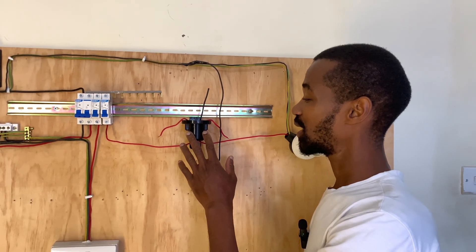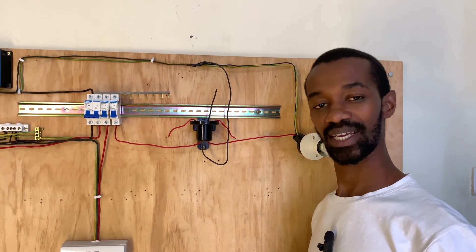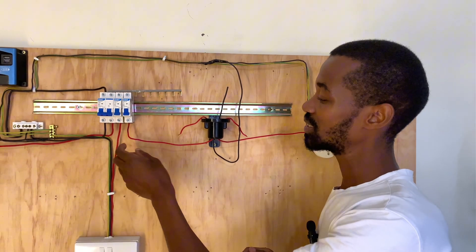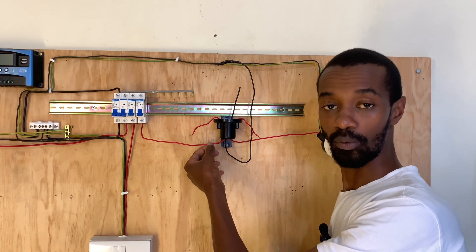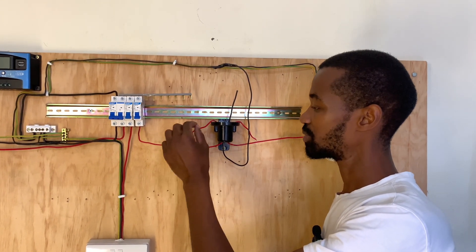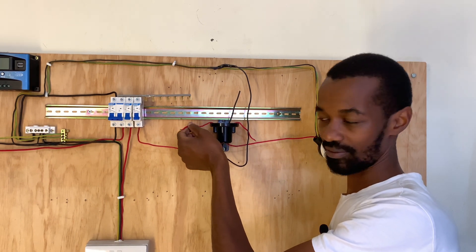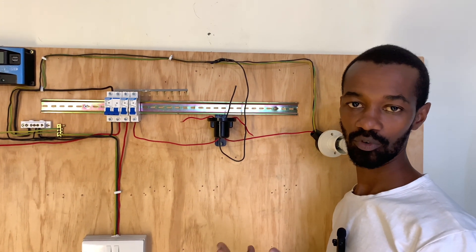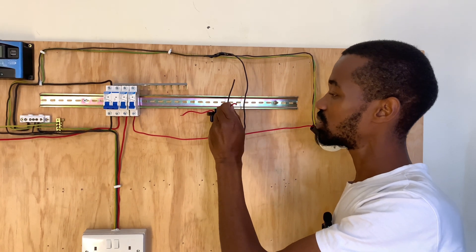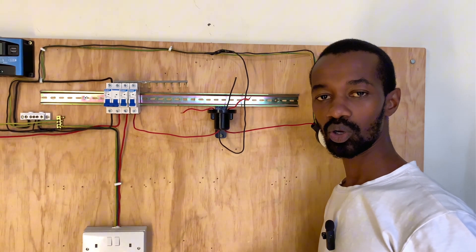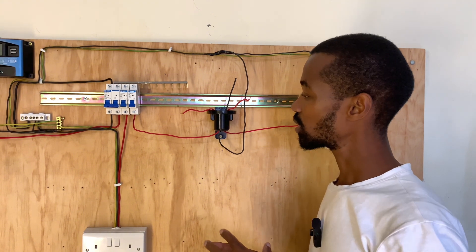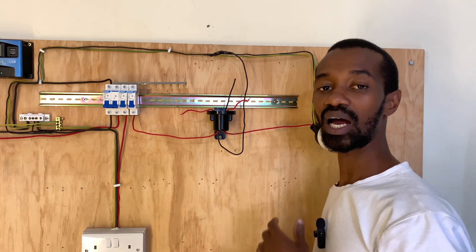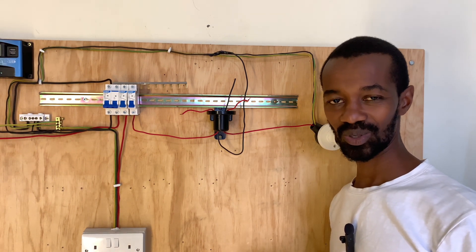Having wired our photo cell, let me recap what I've done. There is an incoming live connection from our MCB — the miniature circuit breaker. Then we have the neutral, which the photo cell requires as a return for its circuit. And then the output, which we will connect so that the photo cell is fed with live and neutral and then gives an output which will go to our bulb.